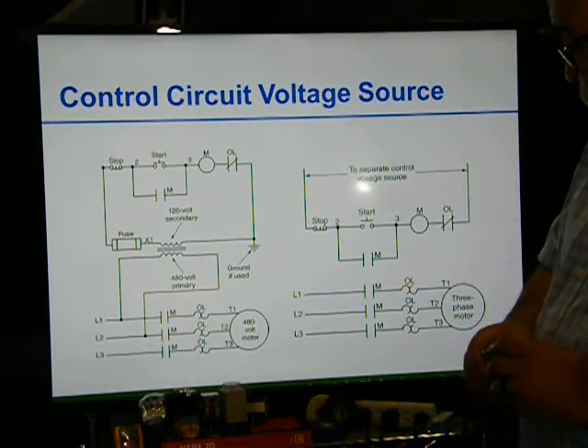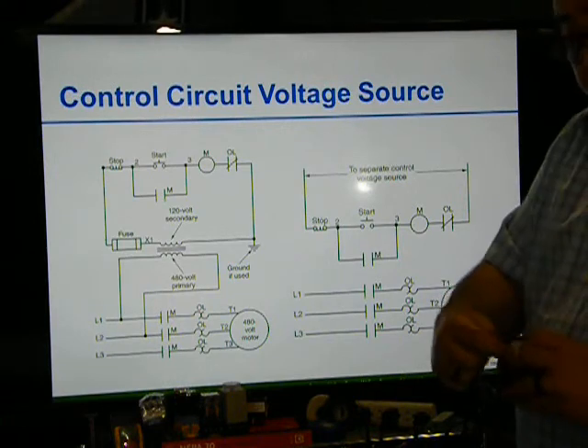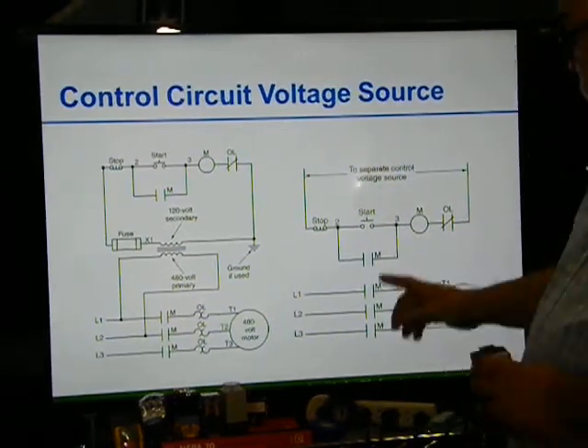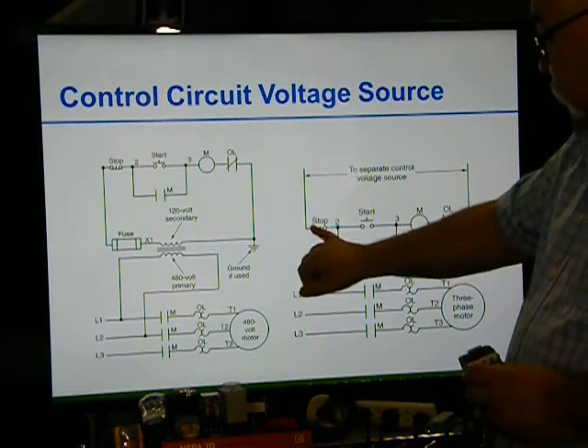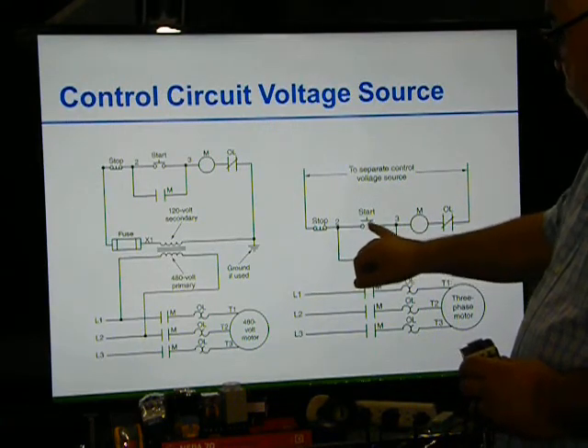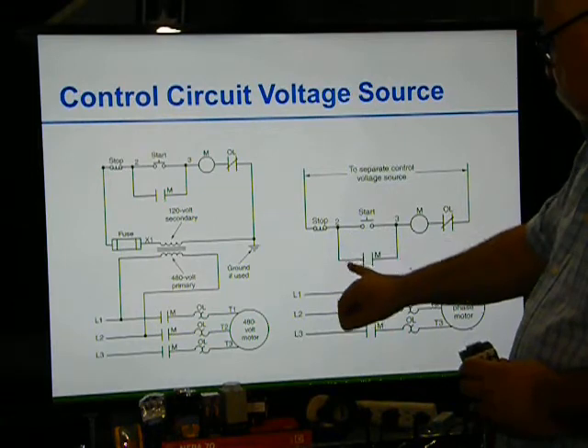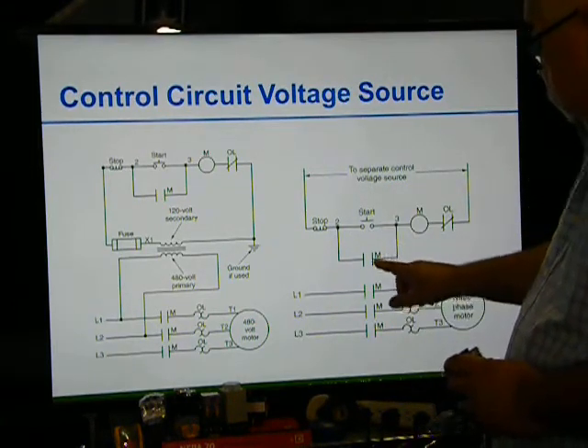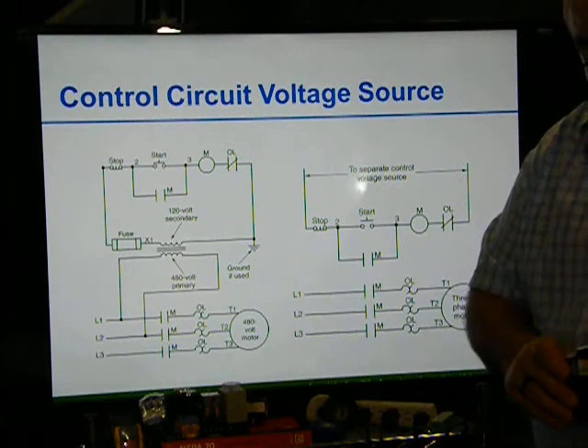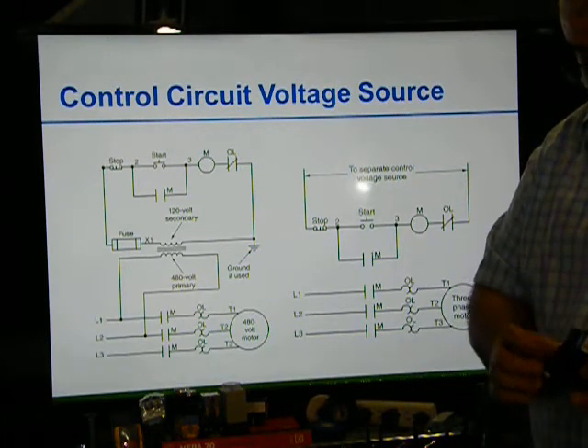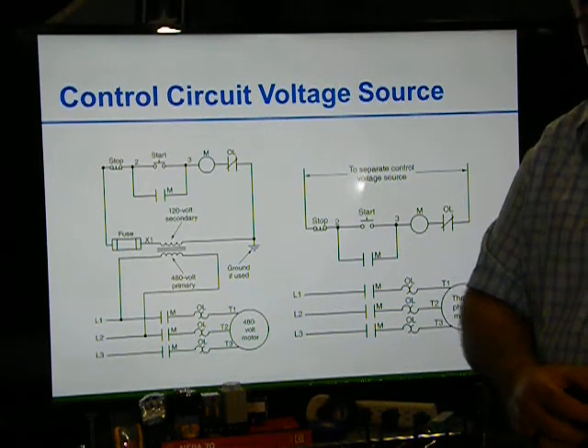or is it right here? It goes to the contactor. So this is on one side, my 3. The way I draw it is I put 1, 2, 3, 4. So from here I'm going to come down, go to my 3. And from here I'm going to come down and go to my 4. Off my 4, I'm coming down and I'm going to my A2, which would be that auxiliary contact.